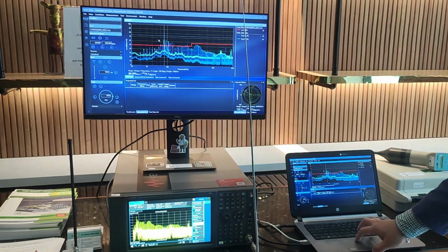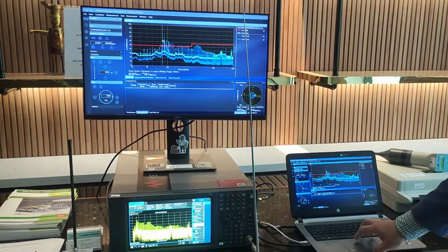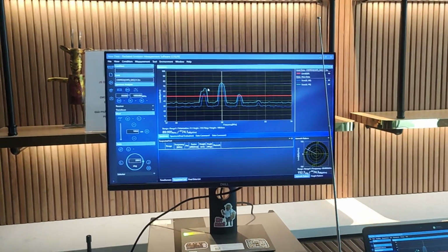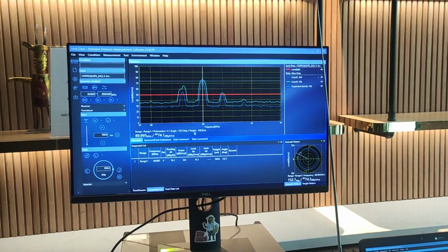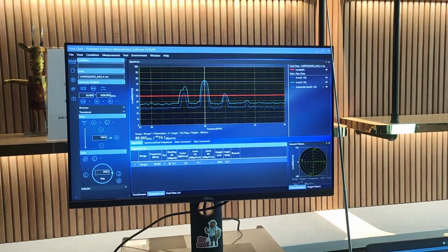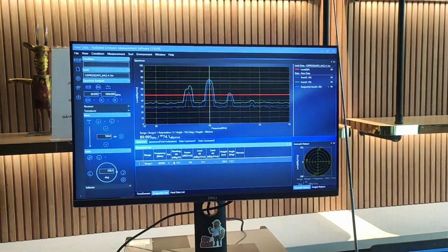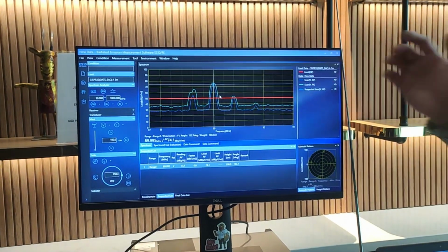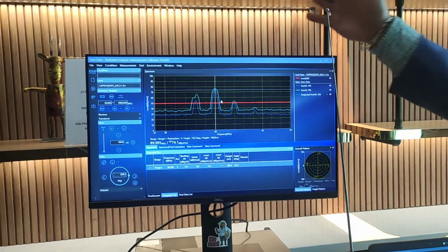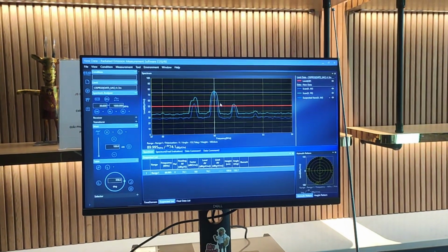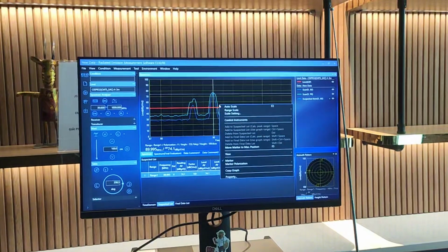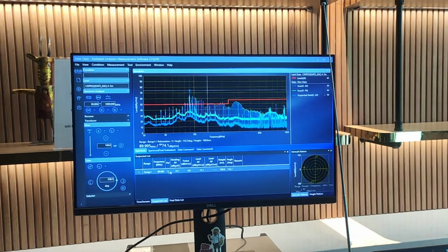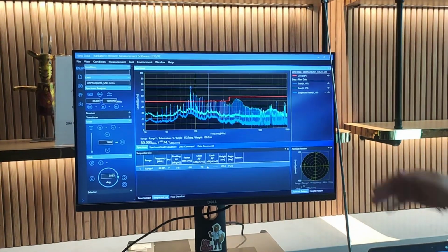Now I know there are a few frequencies here, so I can zoom in and select the point over here. I know that 89.995 exceeds the limit. But of course, now we are in an open environment. This is actually an FM noise, not an actual noise. Then I know this level exceeds the limit.